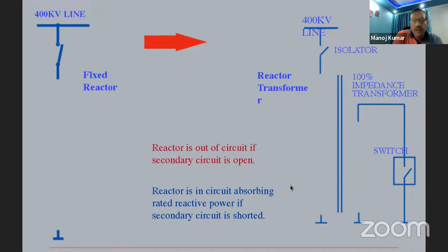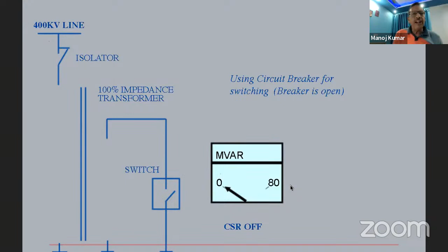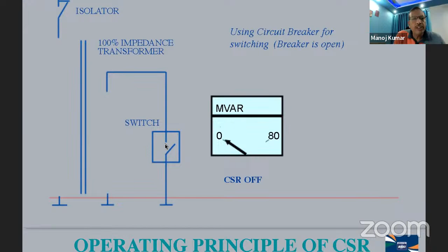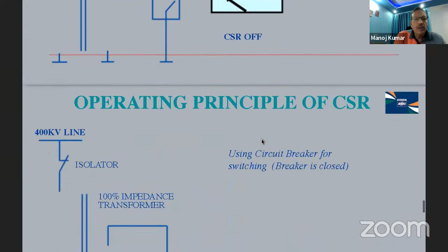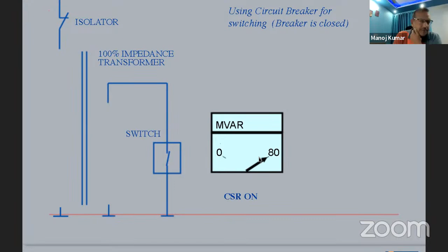These reactors are continuously drawing power from the network even if not required, though reactors are meant to engage whenever the voltage is higher than desired. So BHEL has developed transformers that are basically shunt reactors with a secondary winding. This secondary winding is connected through a circuit breaker, a low voltage winding, let's say 33 kV. Whenever this secondary is open, it does not draw any current from the network, and MVAR is 0. Whenever I close this breaker, it draws the complete reactive current from the network, and the complete reactor comes into the picture.